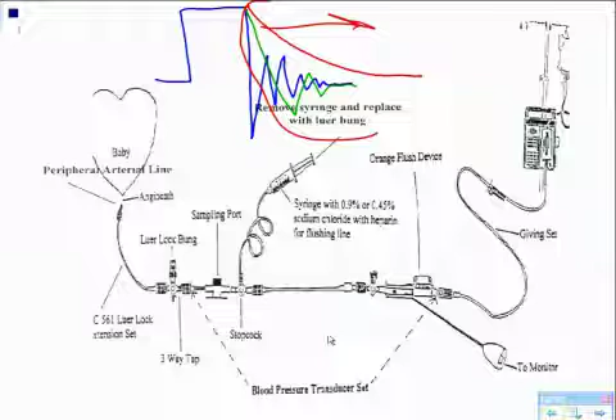But that's how you figure out. That's part of the square test. The square test just tells you if your pressurized bag is working properly, okay? But the resonance portion, which is when you let go of it, that tells you the integrity of the line, of the A line to the transducer. If you have anything between you and the transducer, like air bubbles, blood clot, a kink in the catheter from an A line like this, then you'll get a dampened waveform.